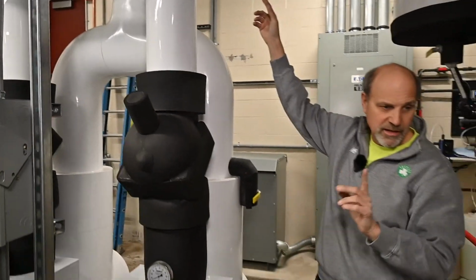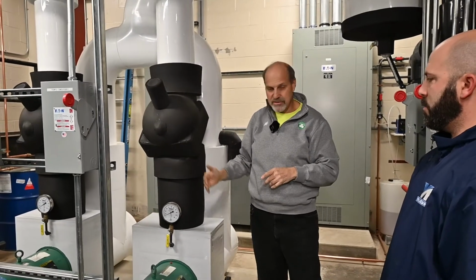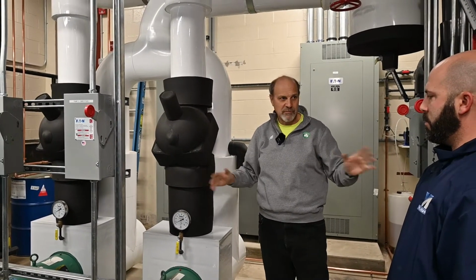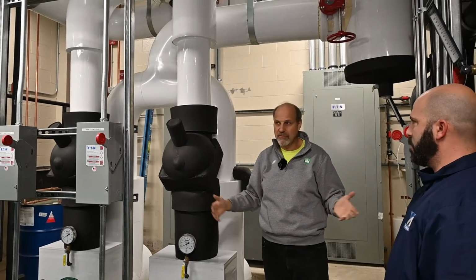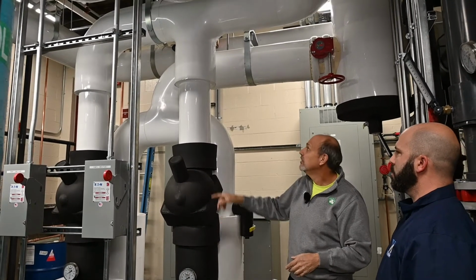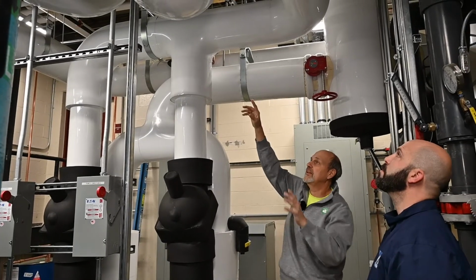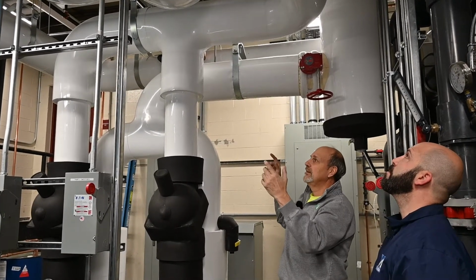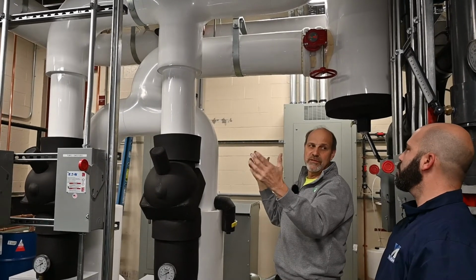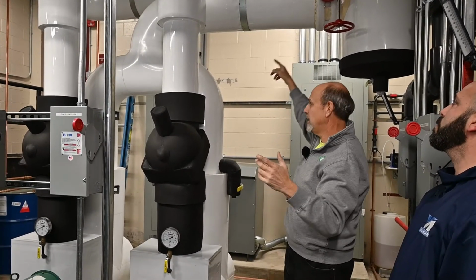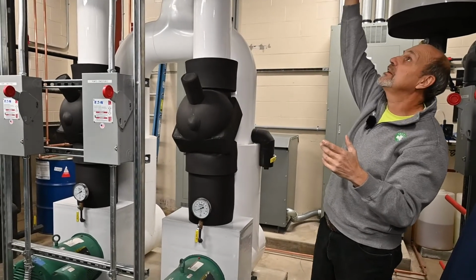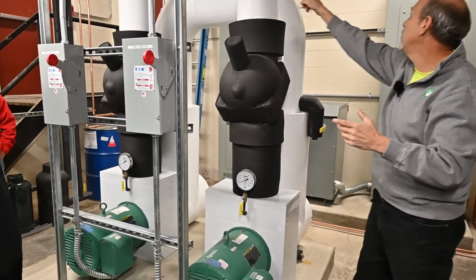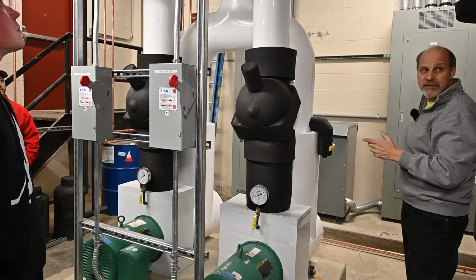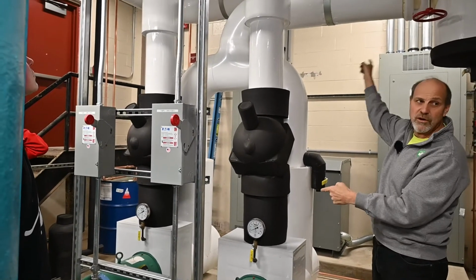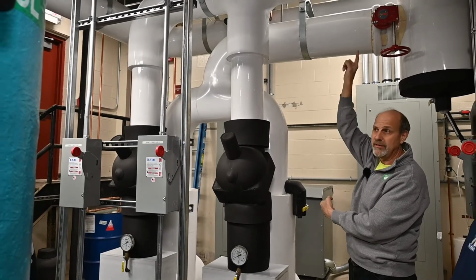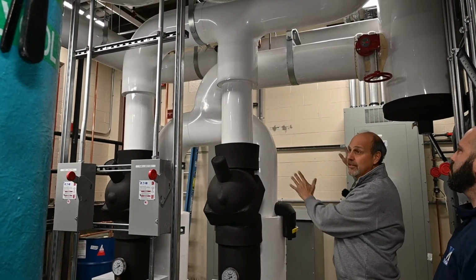All of these pumps in here that I'm going over are really primary and standby pumps. There's always only one pump that needs to run, and there's always a standby pump if one should fail. Comes up in here, it goes through this, and this glycol loop out to the rink, it's basically a primary and a secondary loop. There's two loops here. So if you follow the return back into there, it comes up, it joins together, and all this does is go right back out, back here, and back out to the rink. So all these pumps are doing is circulating glycol through your rink bed. That's all it does. I call that the secondary system.